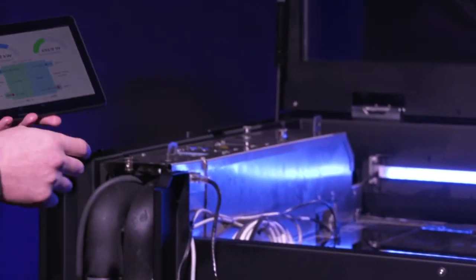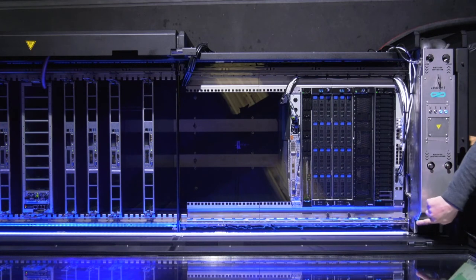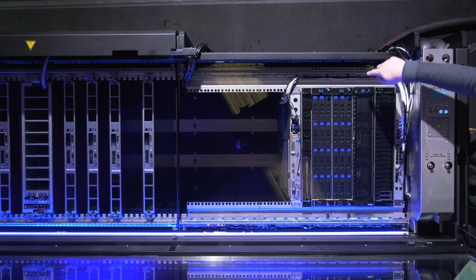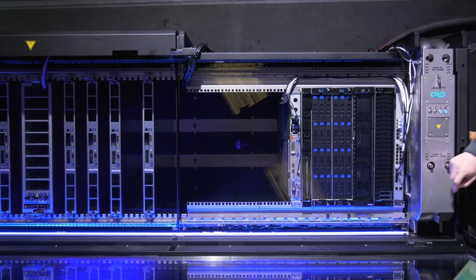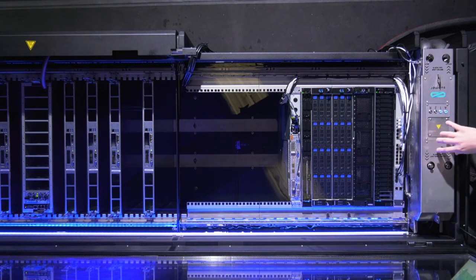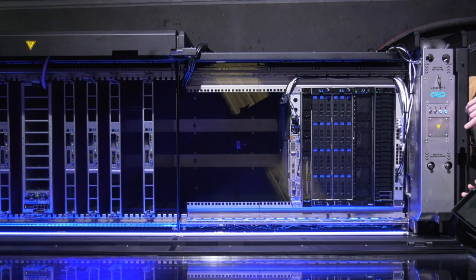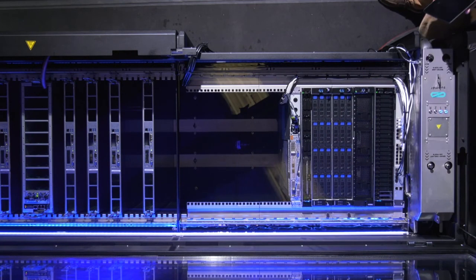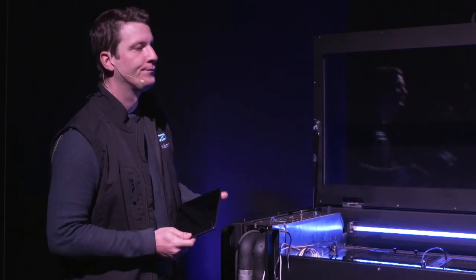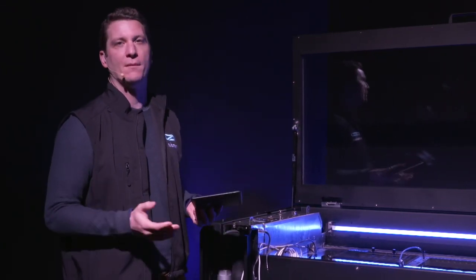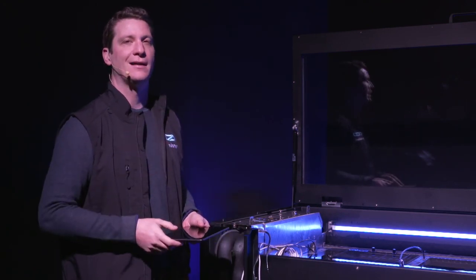We've just had the pump started working. So if we can go into the top camera, what we'll see is how the fluid is being captured along the side channels here, and is running through the CDU to transfer that heat to the heat exchanger and to the water loop, which is definitely not happening now because we've disconnected one of the hoses. All that telemetry is accessible from a SmartPod level API as I mentioned as well, and also, if you have a set of SmartPods, a whole SmartPod farm, we provide a web interface that also allows you to drill down into the farm, see the efficiency of the farm, configure certain values, etc.